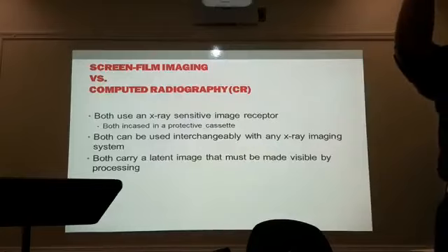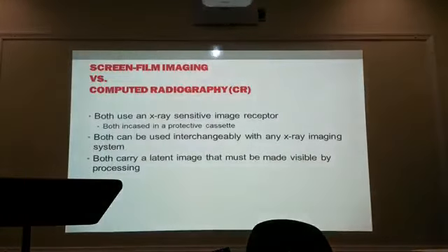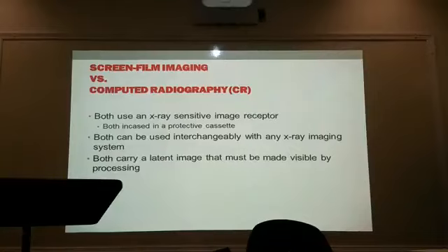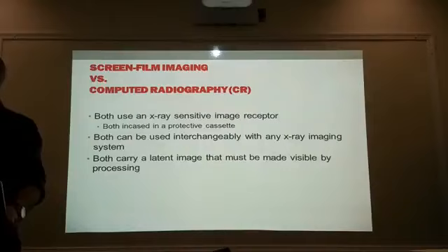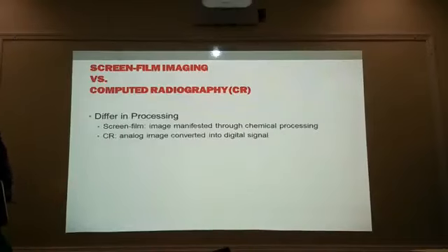The difference between screen film imaging and computed radiography, or CR, is that both use an x-ray sensitive image receptor — in this case, cassettes. One cassette has film; the other cassette will contain the photostimulable phosphor. Both can be used interchangeably with your x-ray equipment, meaning we don't have to exchange or re-outfit our x-ray rooms. Both carry a latent image that must be made visible by processing.